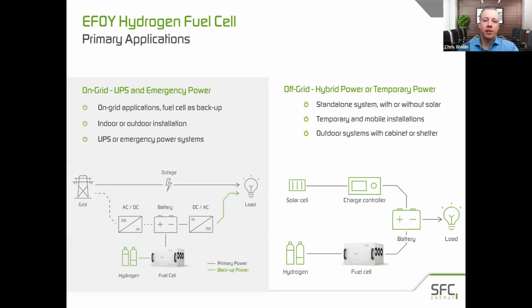Most critical applications are mandated to have at least 72 hours of autonomous backup power to ensure there's sufficient time for the grid power to be restored. And trying to tackle this with battery backup alone can require a pretty substantial battery bank, and running diesel generators to provide backup power can be challenging as well because they don't often turn on when they've sat in standby for too long if they're not maintained properly.